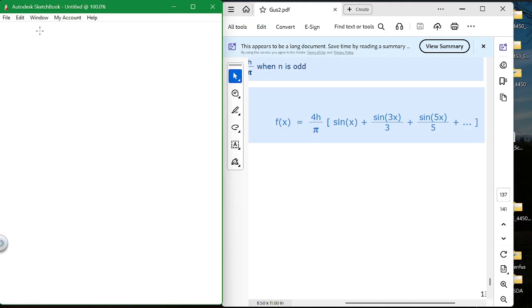I'm going to talk a little bit about the soft starts eventually, but soft starters use SCRs, silicon controlled rectifiers, instead of IGBTs. IGBTs cost more money, but they're higher switching.